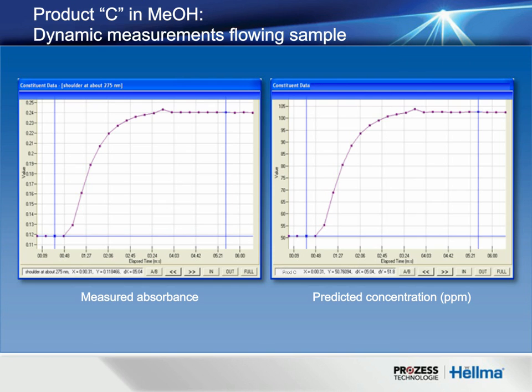Certainly. The sample interface itself is very rugged and robust and has been built for consistent, stable readings. All of the optical components have been tested for the effects of pressure and temperature. They are fixed, and over time you will see very little change due to the sample interface itself. Additionally, the 3A probe has been designed with a leak detection feature: if for whatever reason the seals on the probe have failed and something would start influencing your data, it would drop out and you would know immediately.